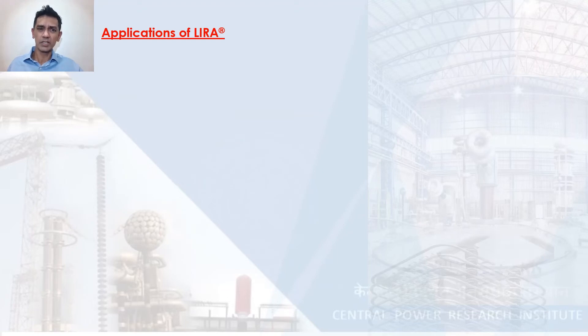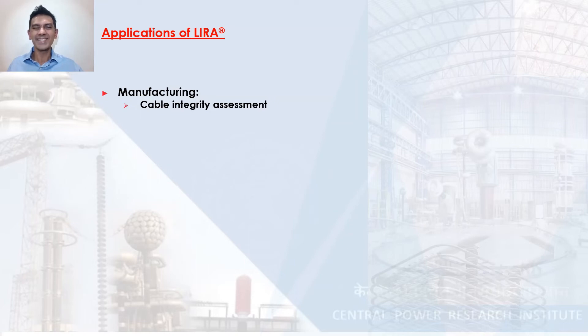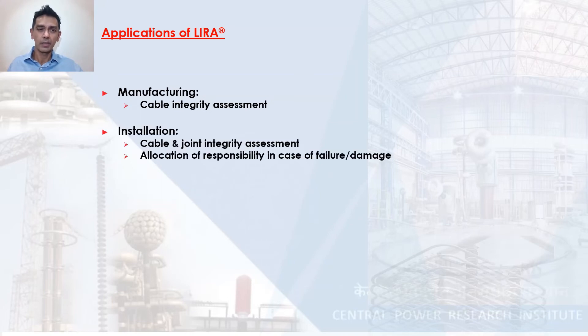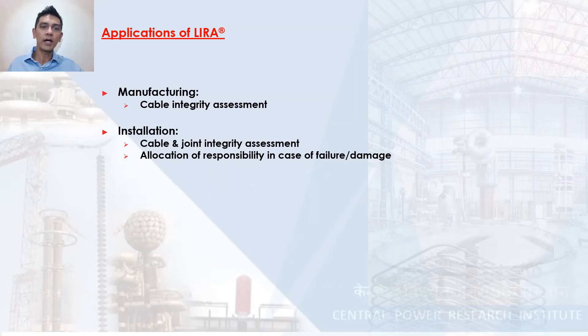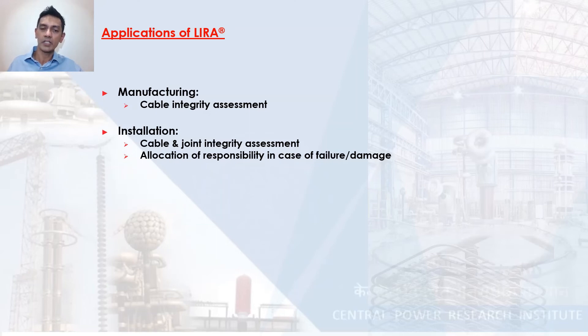Where would you use Lira? In the cable manufacturing process, you would use it to assess the integrity of your cable for quality assurance. When you install cables on site, Lira can assess the condition of the cable, the joints, and the terminations. You can quantify the condition of each and every single joint to decide if the quality of workmanship was acceptable or not. You can also pick up any damage that might have happened to the cable during transportation.